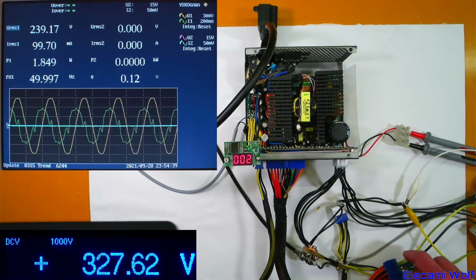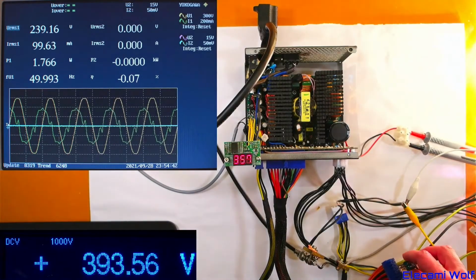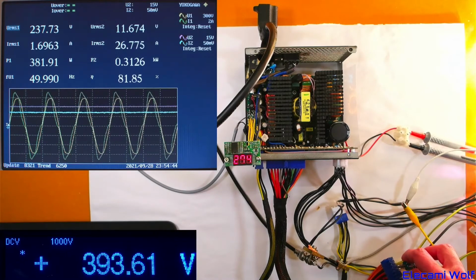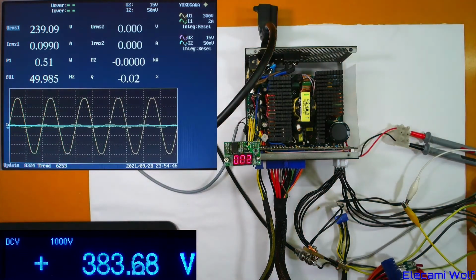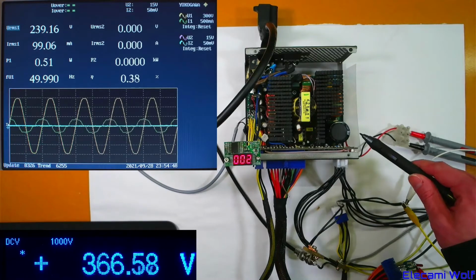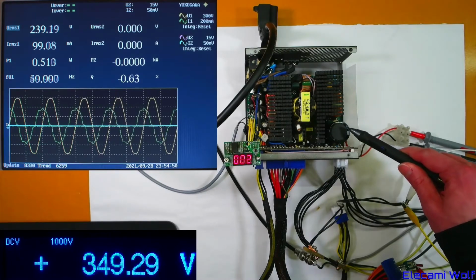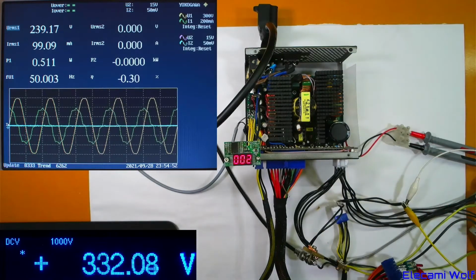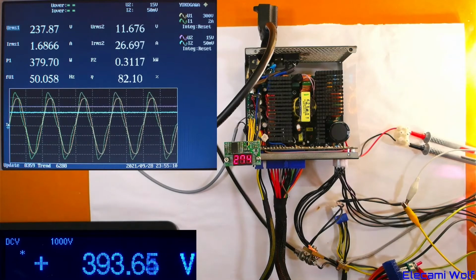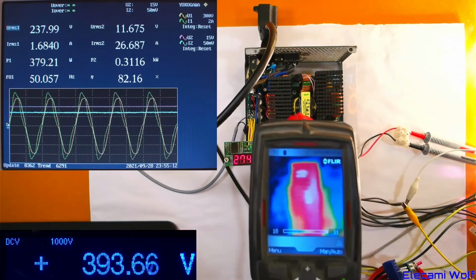Interesting, when we switch on the power supply, the DC bus voltage goes up to 393.5 volts there. That's concerningly close to the voltage rating of the DC bus capacitor. It's only rated at 400 volts, pushing it pretty close to the limit there. Let's have a look how this power supply is performing thermally.